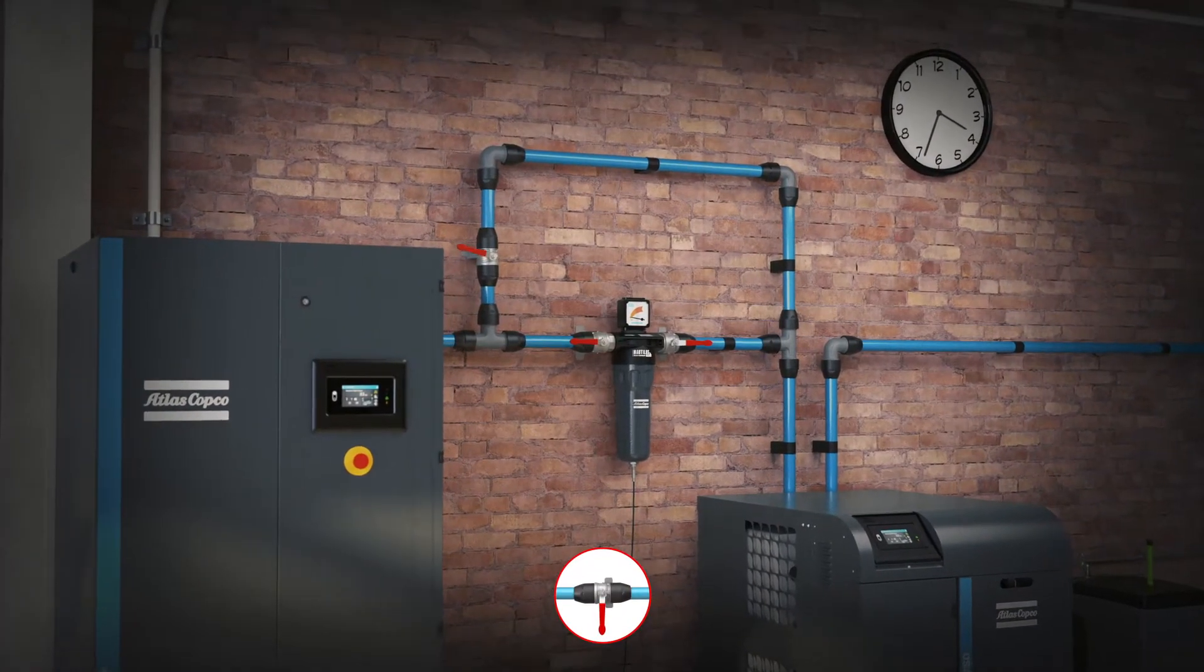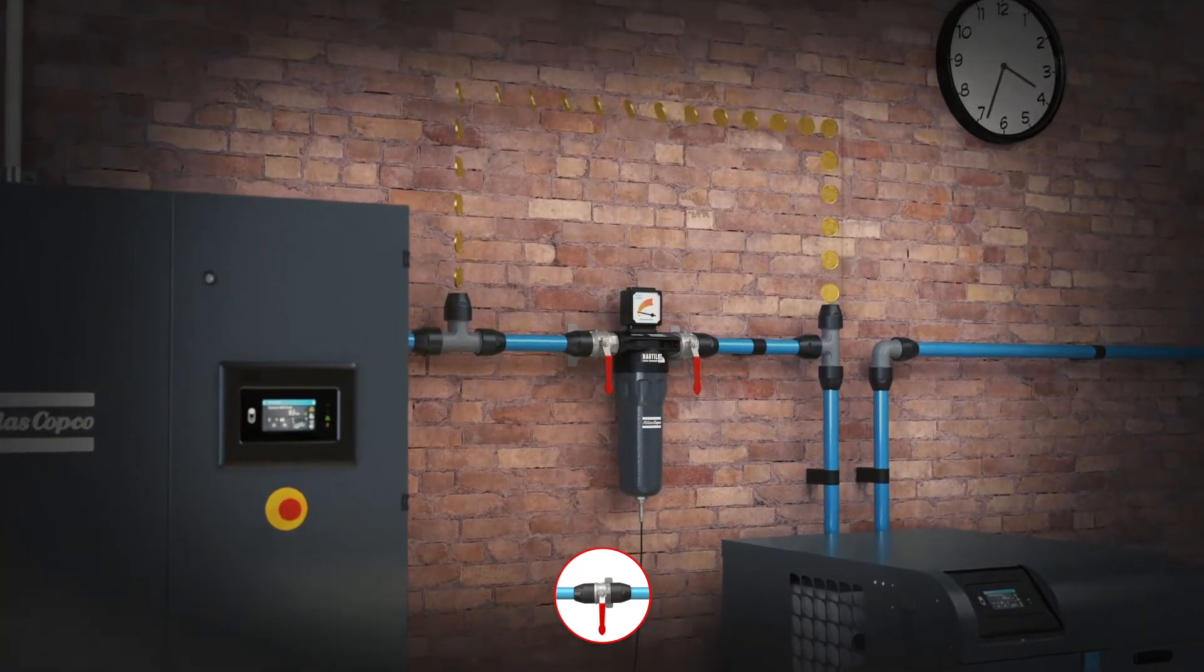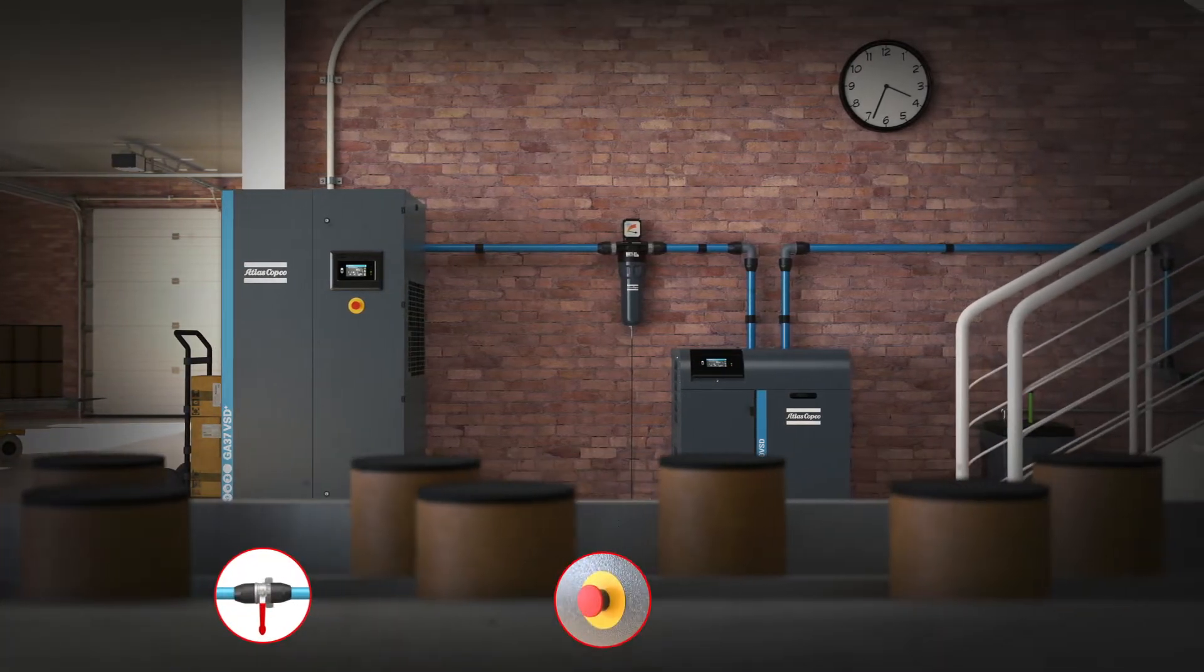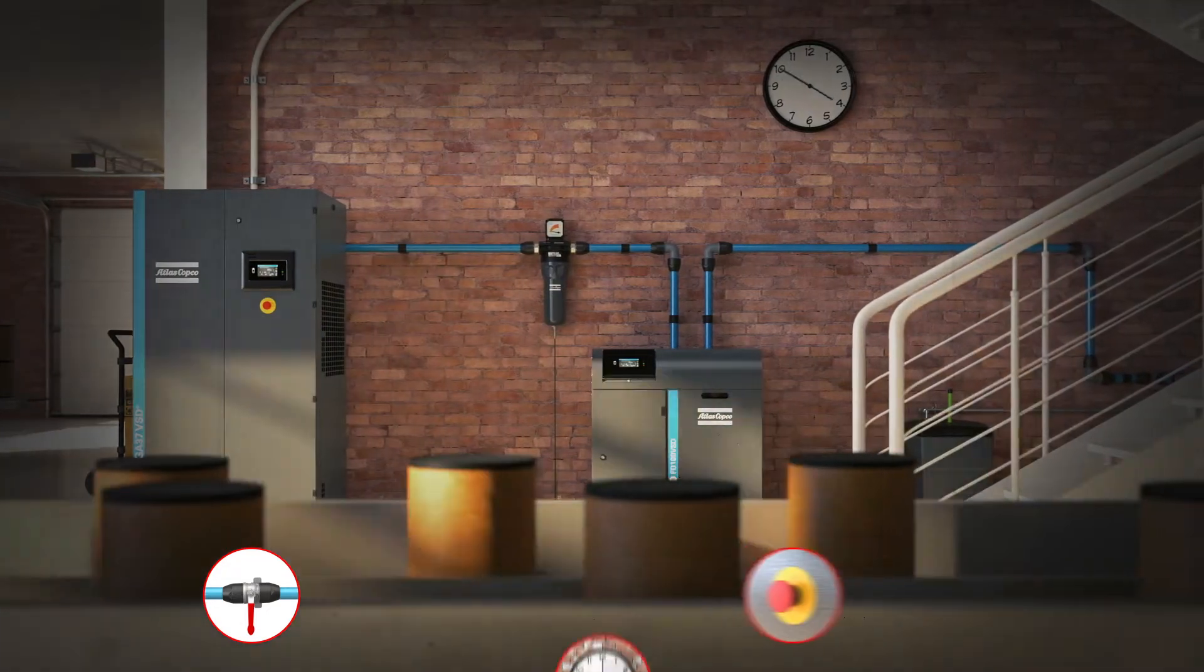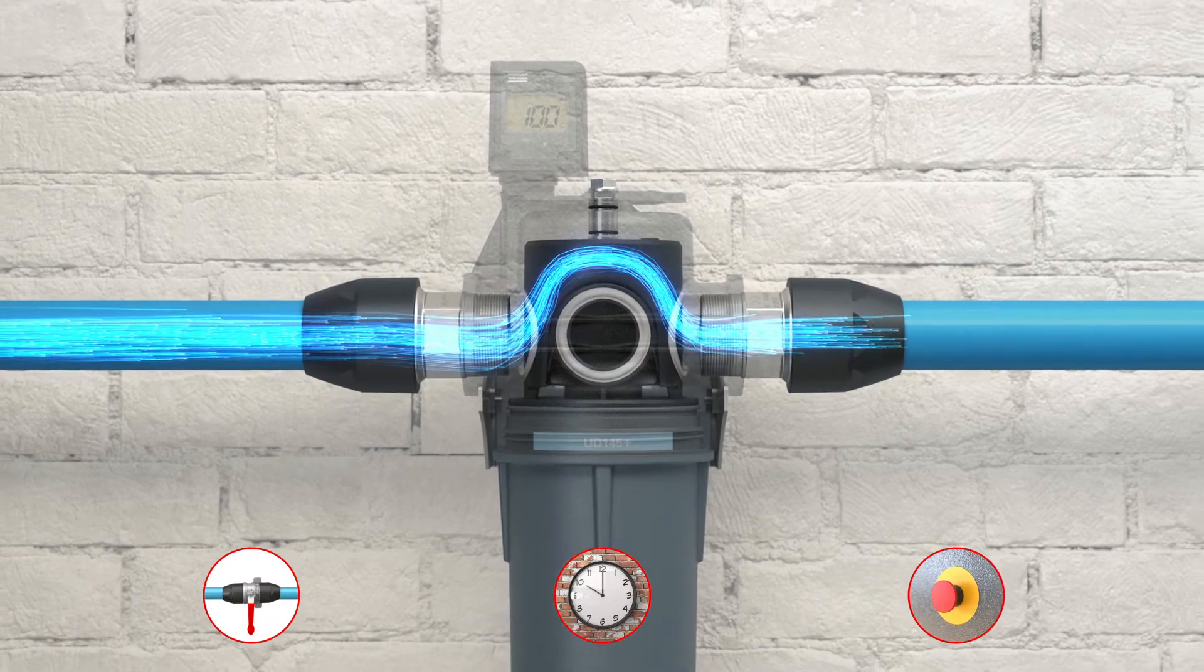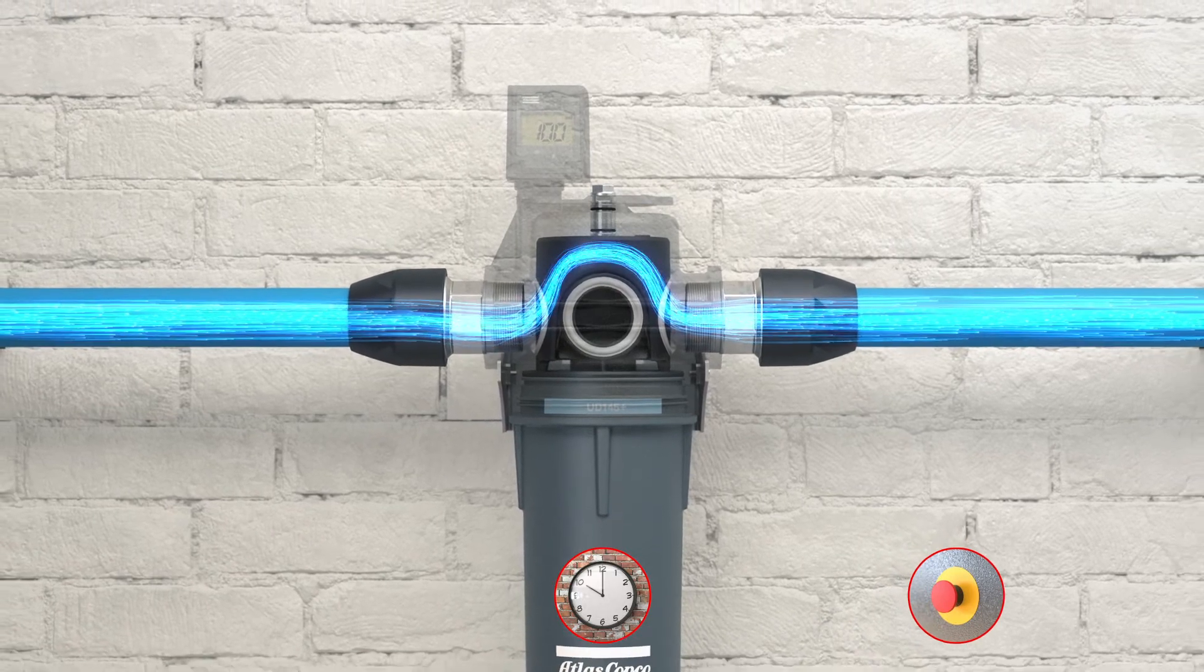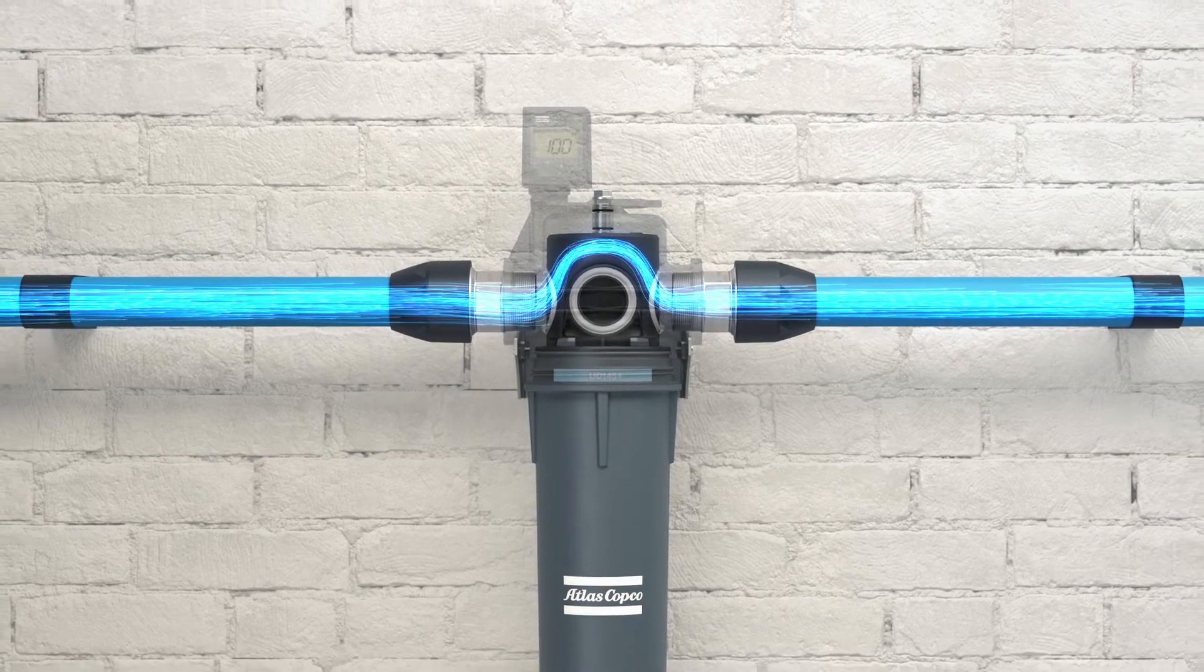Until now, installing an external three-valve bypass was the only way to service your filters without interrupting your airflow. Without this costly bypass, you simply had to shut down your entire air system for filter element replacement during production or after working hours. The bypass routes the air through the filter head during maintenance. No need to install extra piping around the filters, no need to halt production, no need to schedule filter maintenance after working hours. It's truly seamless service for the first time ever for maximum cost savings.